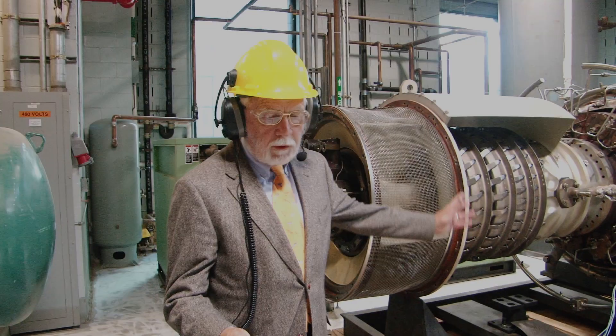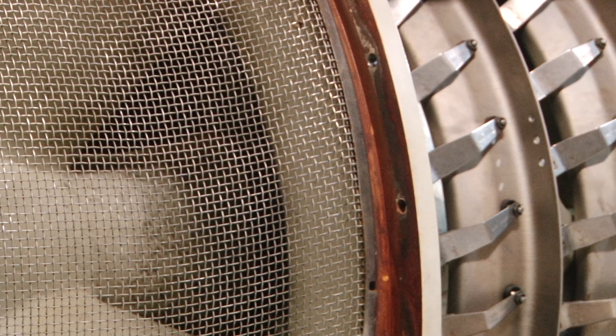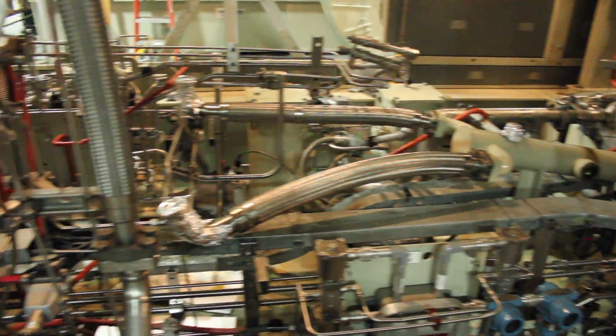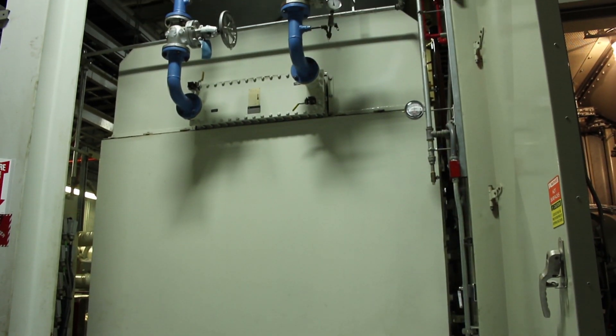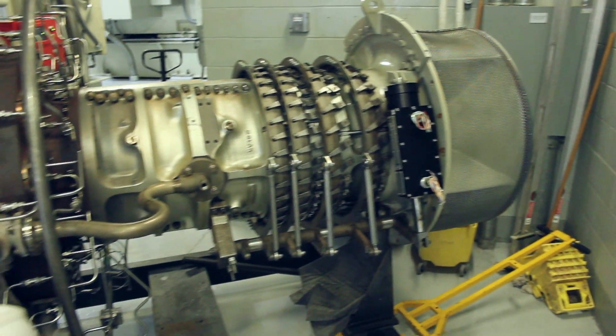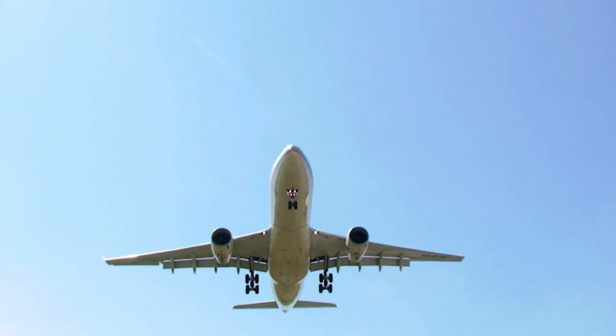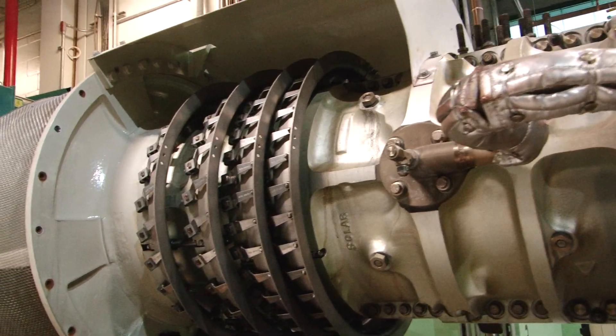This is a gas turbine, a Solar Taurus 70, one of three that is the heart and soul of UConn's 25-megawatt co-gen power plant. This Taurus 70 has been in operation at the UConn plant for over 41,000 hours and has just been replaced by another unit after a record-breaking operational life of about five years, and is being shipped out for overhaul. It drove a generator to produce as much as seven to eight megawatts of electric power, or about 10,000 horsepower in automotive terms. One megawatt is about 800 households of power. This Taurus 70 is about one-third the size of the jet engine on a Boeing 737, such as those used by Southwest Airlines. It has a thermal efficiency of 34%, costs about $1.5 million, and rotates at about 15,200 RPM.